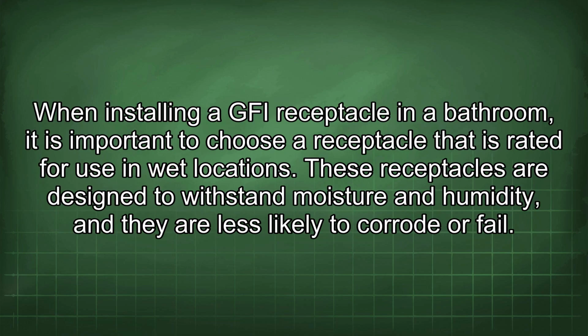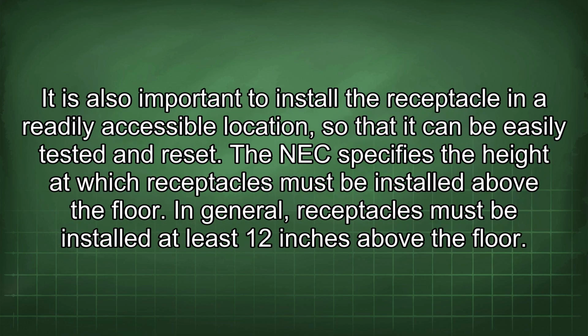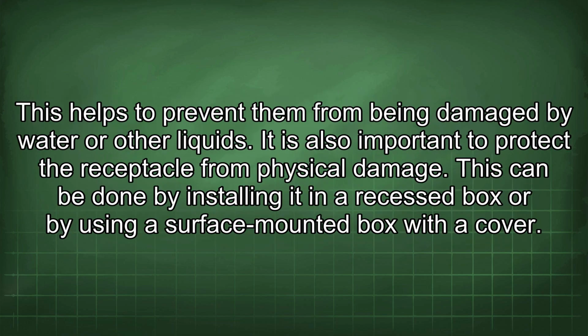When installing a GFI receptacle in a bathroom, it is important to choose a receptacle that is rated for use in wet locations. These receptacles are designed to withstand moisture and humidity, and they are less likely to corrode or fail. It is also important to install the receptacle in a readily accessible location so that it can be easily tested and reset. The NEC specifies the height at which receptacles must be installed above the floor. In general, receptacles must be installed at least 12 inches above the floor. This helps to prevent them from being damaged by water or other liquids.